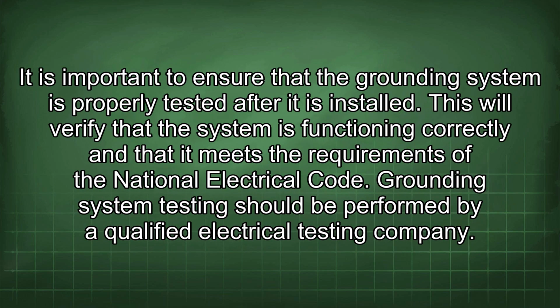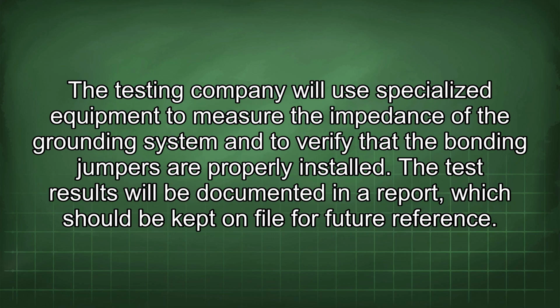It is important to ensure that the grounding system is properly tested after it is installed. This will verify that the system is functioning correctly and that it meets the requirements of the National Electrical Code. Grounding system testing should be performed by a qualified electrical testing company. The testing company will use specialized equipment to measure the impedance of the grounding system and to verify that the bonding jumpers are properly installed. The test results will be documented in a report, which should be kept on file for future reference.